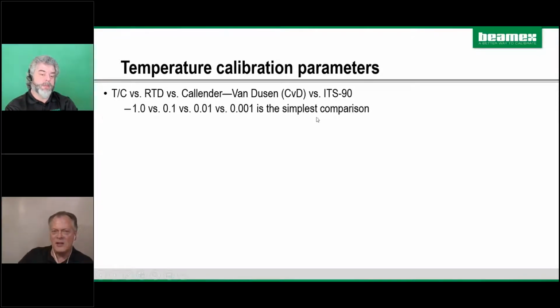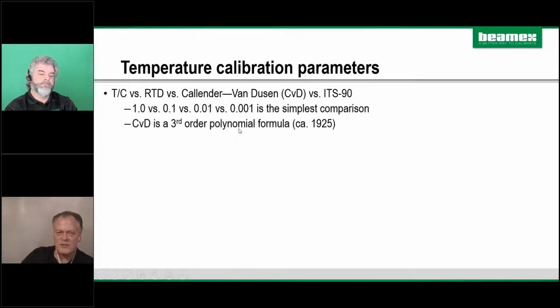In the simplest terms, thermocouples are accurate to so many degrees. RTDs are accurate to tenths of a degree. If you have a 3-wire RTD, it might be closer to 1. If you have a 4-wire RTD, it's closer to 0.1. You can also buy more expensive RTDs and have a special calibration done against those. There's a long-time formula called Callendar van Dusen, which gets you out to hundredths of a degree. And if you're really after high accuracy, there's an ITS-90 formula that gets you beyond thousandths of a degree. We'll admit this is an oversimplification, but it's just an example of the differences in these items from a high level.